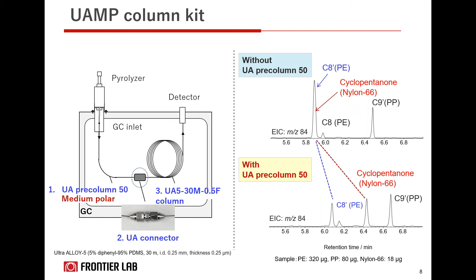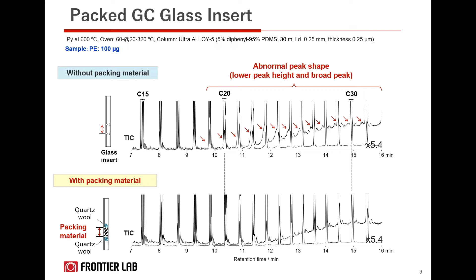Now moving on to another part of the complete solution for microplastics, the packed GC glass insert. We also developed a packed GC glass insert, pretty much your liner for your GC, to improve the peak shape of the pyrolysates generated from microplastics. In addition to a better peak shape, the packed GC glass insert can improve the accuracy of your qualitative and quantitative analysis of a specific plastic in a polymer mixture sample using F-Search MP 2.0 software. And you can see an example here of how the abnormal peak shape and the lower peak height are improved when you are using that packing in the GC glass insert.